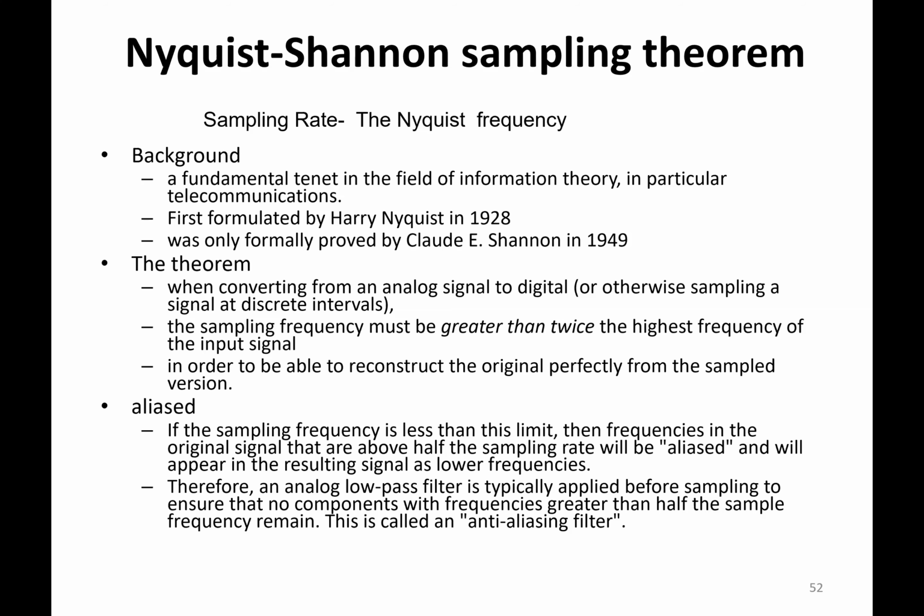To prevent that from happening, we use a low-pass filter. Are we together? An instrument usually has low-pass filters to prevent aliasing, because if you sample at less than twice, at least twice that, and you sample at a half, then you are going to have some other frequencies coming in. It makes it difficult for us to interpret what those peaks are.